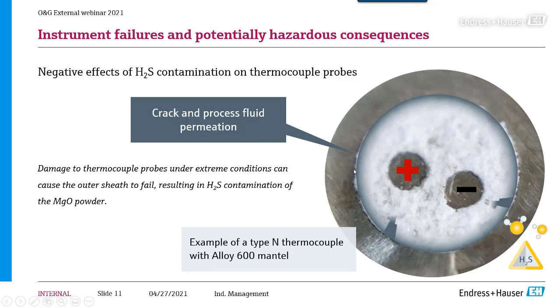From the external part, this pollution will also reach the internal wires, the conductors or electrodes. It's a matter of time, depending on physical factors like how big the crack is, how compact the powder is, and how much pressure is inside the vessel. But it's just a matter of time, maybe a couple of days, maybe a couple of months. The pollution will reach the internal wires of the thermocouple, and from there it will spread again around.